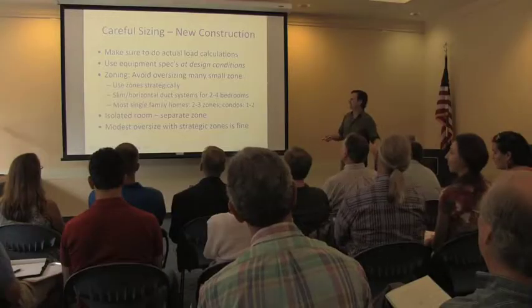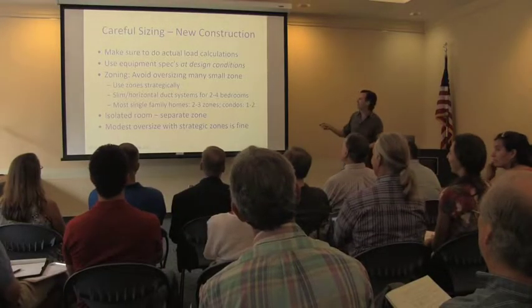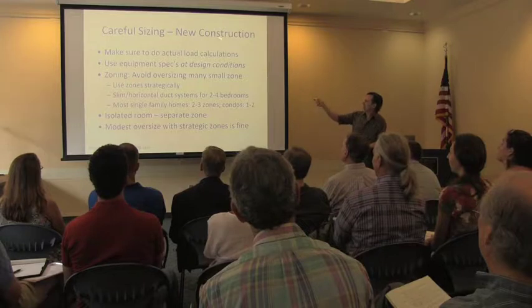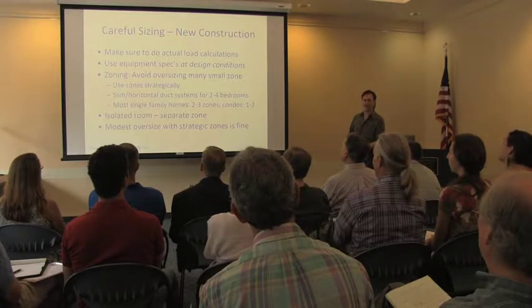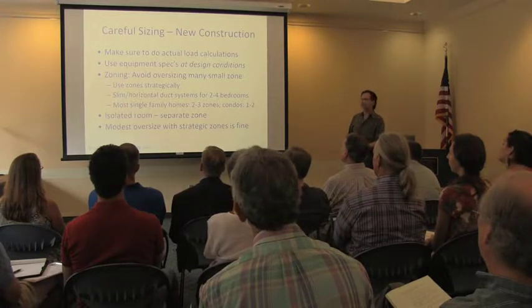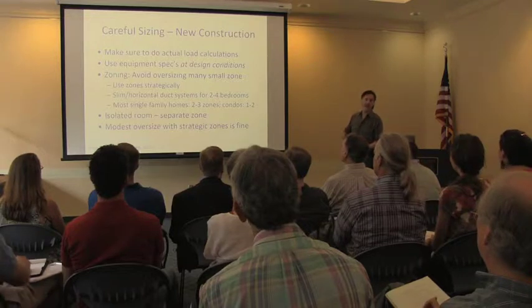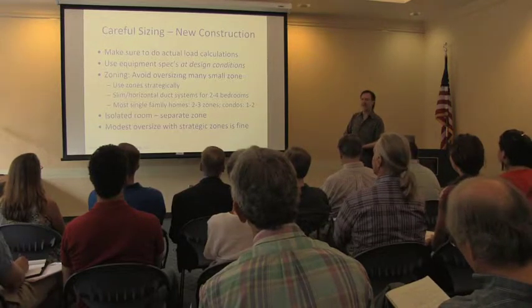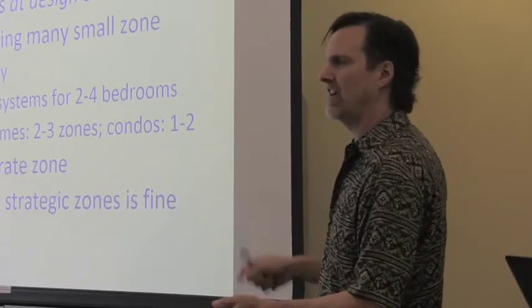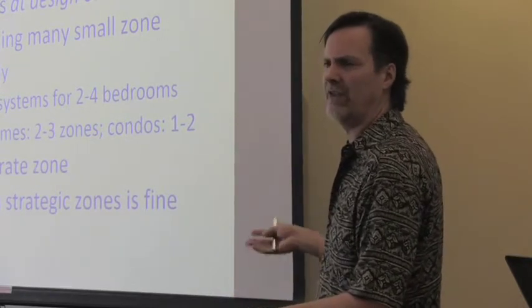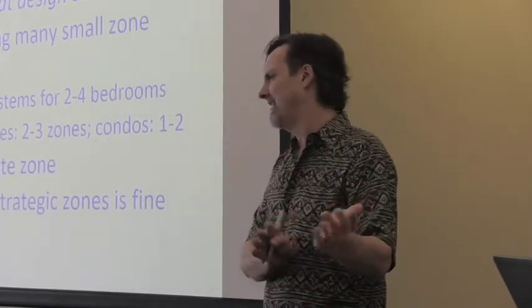A few ideas, just points to make about things to pay attention to. Make sure that you size them carefully. If you're going to produce all of the heating for a house, you want to make sure that the machine will generate that heat at your outdoor design condition. Around here, that design temperature is, what, plus 5 or plus 3 degrees Fahrenheit, something like that. We know it gets colder than that, but it's not that many hours a year that it's colder than that.